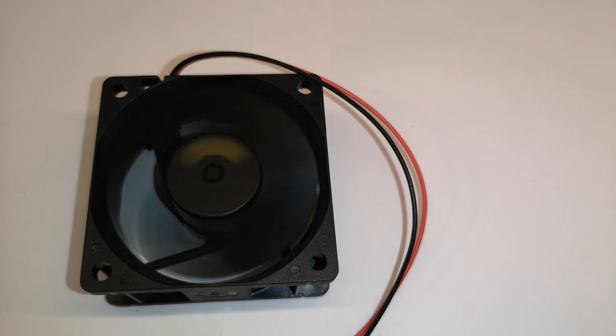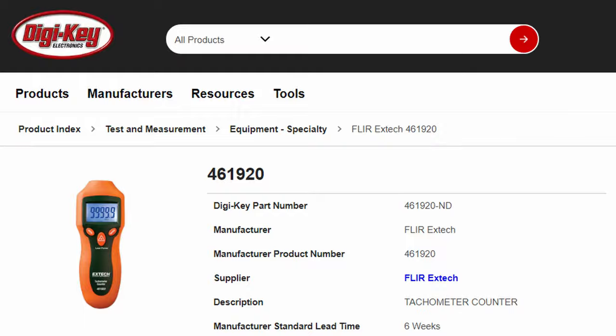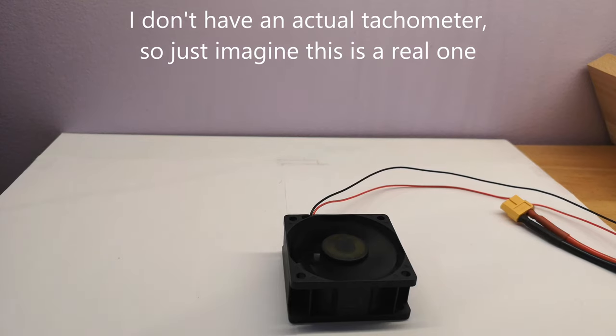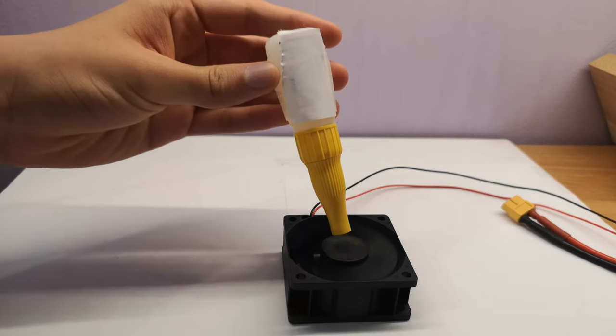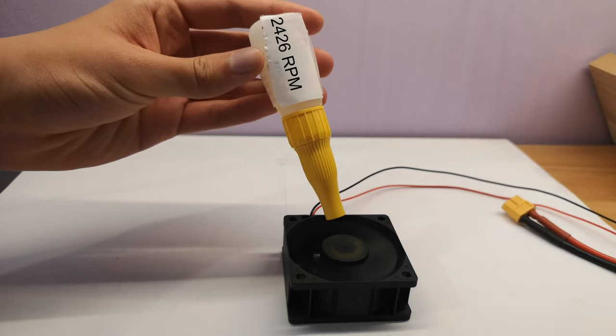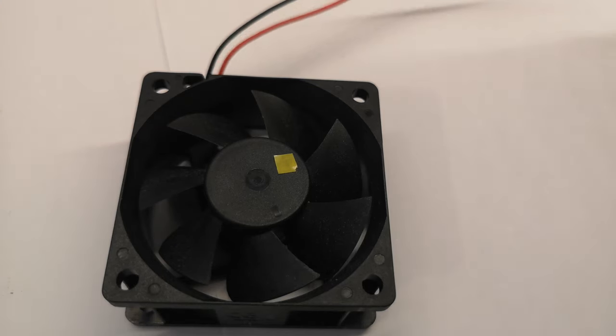Usually, it is more preferable to use a contactless method, such as using a laser tachometer, which works by measuring the frequency of a changing reflected laser beam. The pros of these devices include the fact that they are quick and easy to use, and they can be extremely accurate. However, this method relies on automatic signal processing, which can be unreliable, especially in suboptimal conditions.